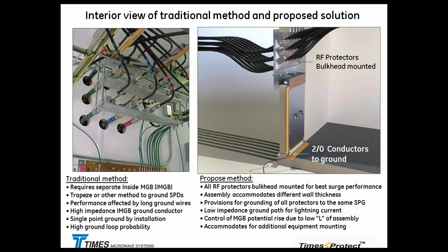If you take a look internally at the proposed solution, the cables come here, you do a natural transition high for the jumpers, you put feed-through protectors, or you put a blank plug if you don't have enough feeders, or you can put a feed-through for people who hate lightning protectors. You can put basically feed-through connectors, and you are capturing all your ground. No grounding kits on the outside. You've got a nice, beautiful flat bulkhead mount for all the protectors, and then you've got an adjustable plate right here, an 18-inch wide plate. You tie a couple of 2/0 wires, basically short pigtails, go through the shelter, and you cadweld them to the outside of the ring. You are done, nothing to steal.